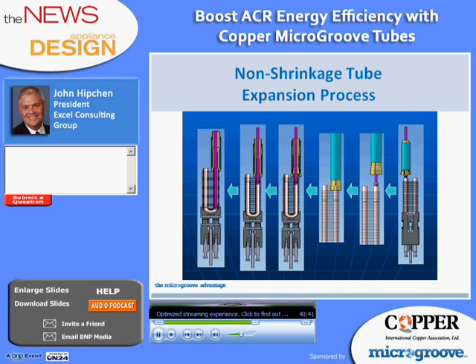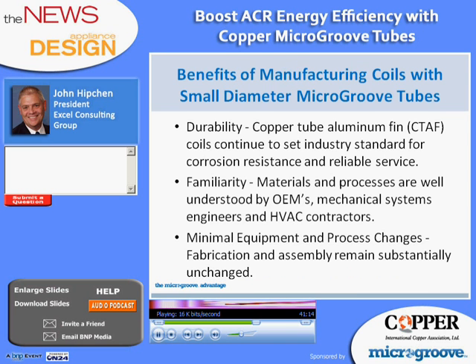As smaller diameter tubes are expanded, axial tube shrinkage can become a problem, and the International Copper Association's team in China supported the development of cost-effective tube expansion technology that controls tube shrinkage and maintains tension on the expansion tools for high manufacturing yields and long tool life. This technology basically secures the tube end during expansion in order to prevent shrinkage. So this method of manufacturing coils continues to set the industry standard for corrosion resistance and reliable service life. Since this process remains largely unchanged for small diameter microgroove tubes, engineers and technicians throughout the industry are familiar with the practices and also the costs associated with it.